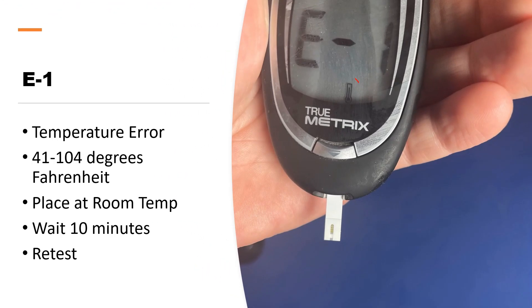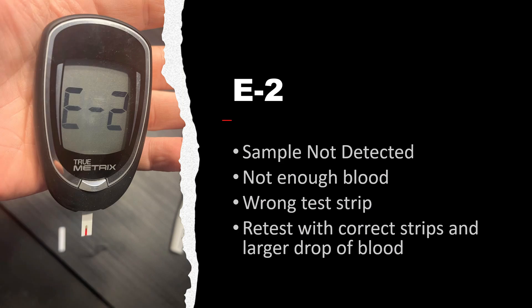E1 indicates that the meter is being used at a temperature out of the recommended range. It's recommended you use it between 41 and 104 degrees Fahrenheit. If you get this error, place the meter at room temperature, wait 10 minutes, and retest.